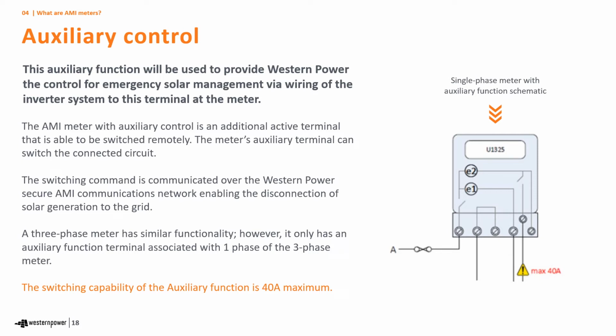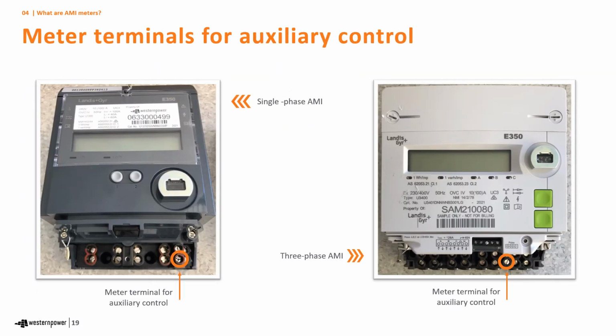A three-phase meter has similar functionality, however it has an auxiliary function terminal associated with one phase of the three phase. You can see here the second element in the switching of that element, which will be used for controlling the solar system. Not that you need to know this, but we've also shown you the load control terminal where our metering technicians will connect the cable left by the installers to the meter to enable meter control on a single phase and then on a three phase.